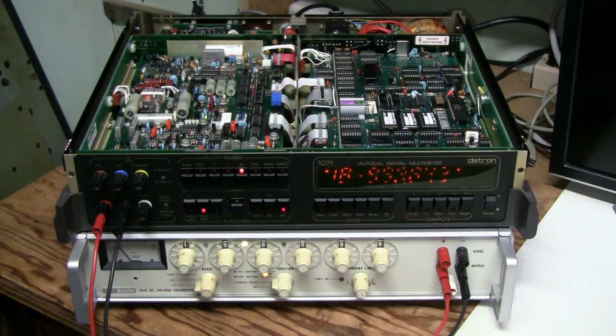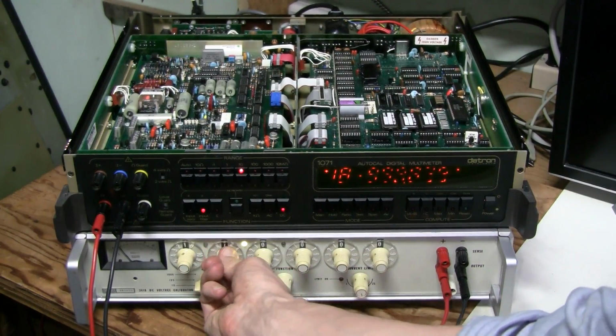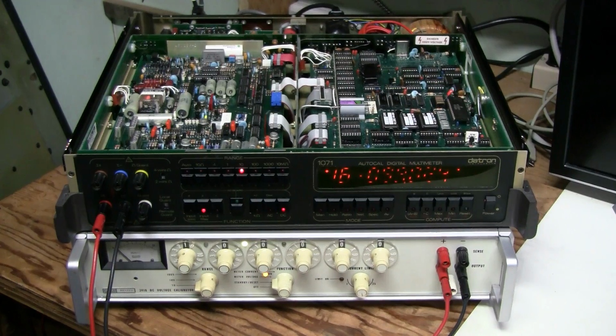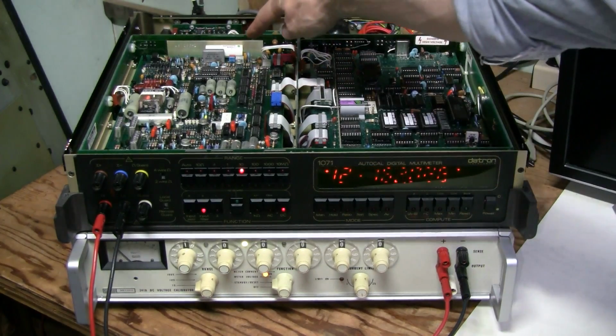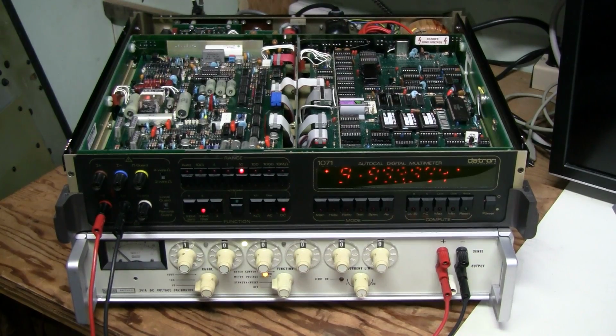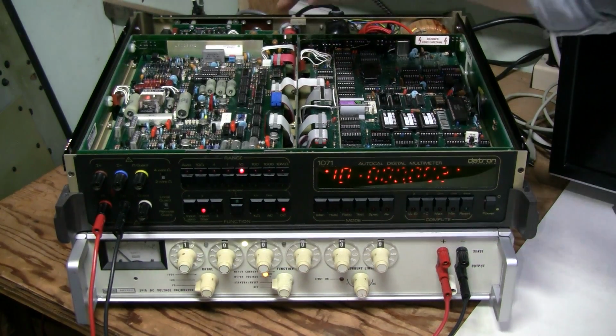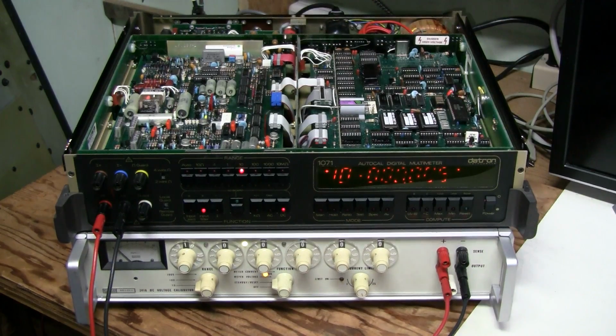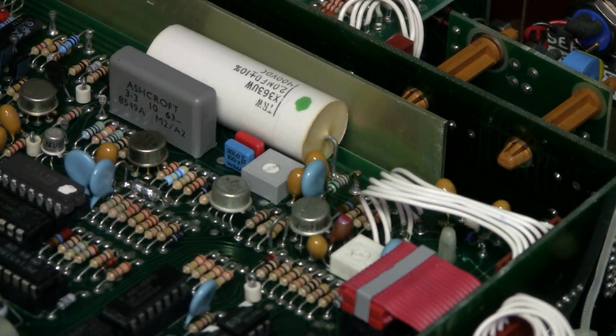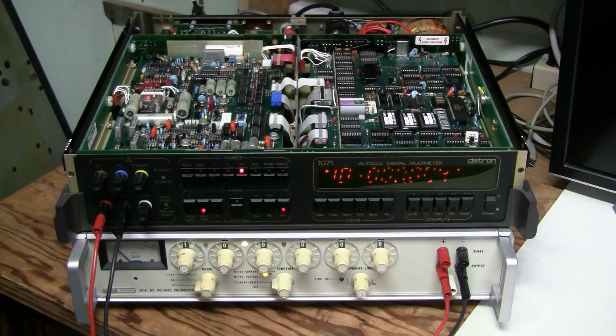So this reading needs to be subtracted from 19 and the resulting error divided by 2, and then we need to set 10 volts again and adjust this trim pot here by that amount. And I tried doing that, but hit the limit of the trim pot. And there is a factory selected resistor on special standoffs close to that trim pot. It can be adjusted to shift the range of the trim pot if necessary, but I don't think it is a good idea.